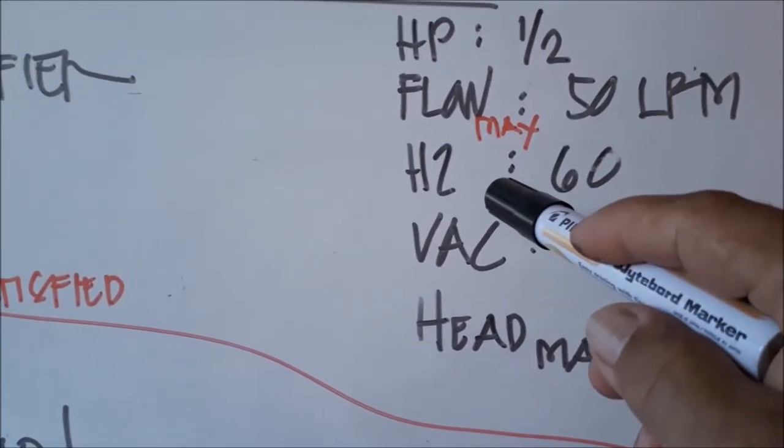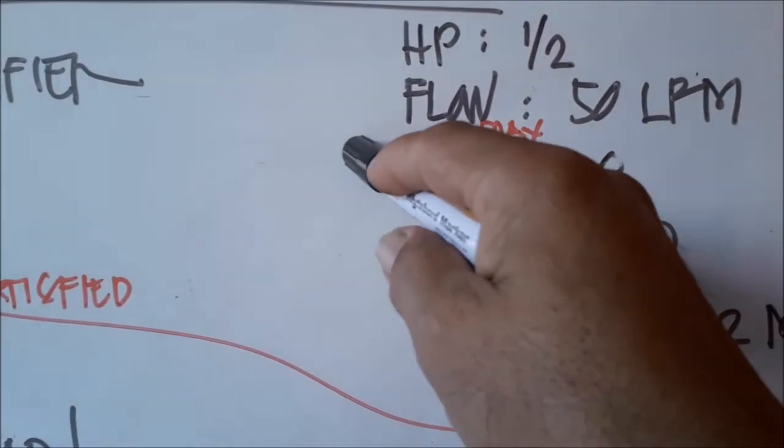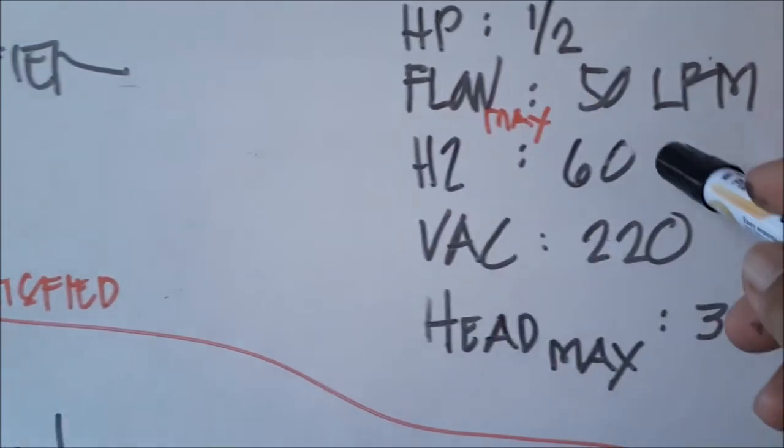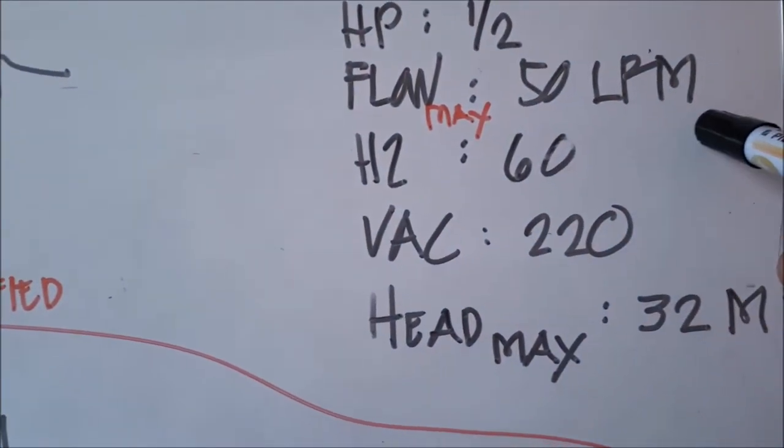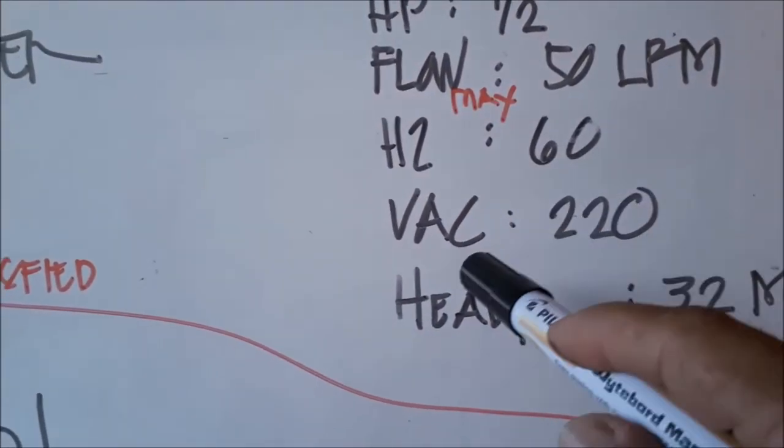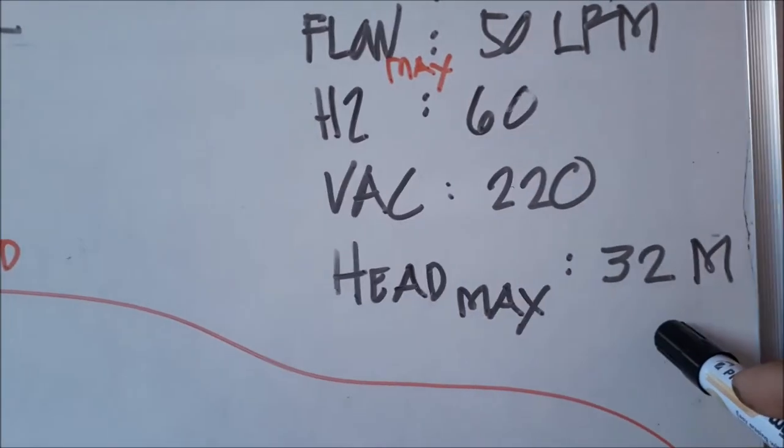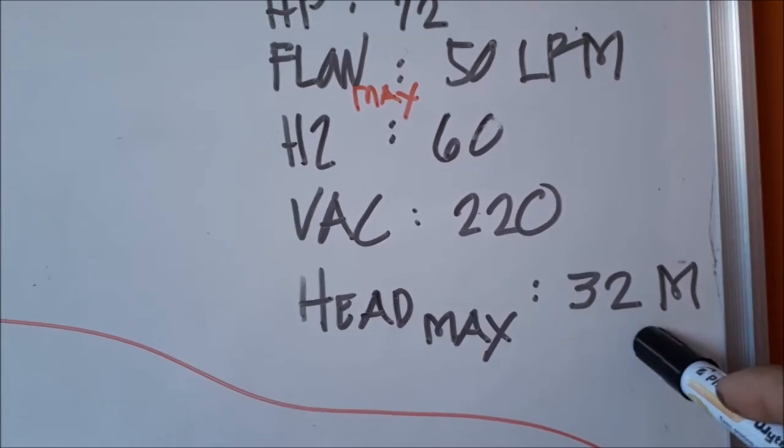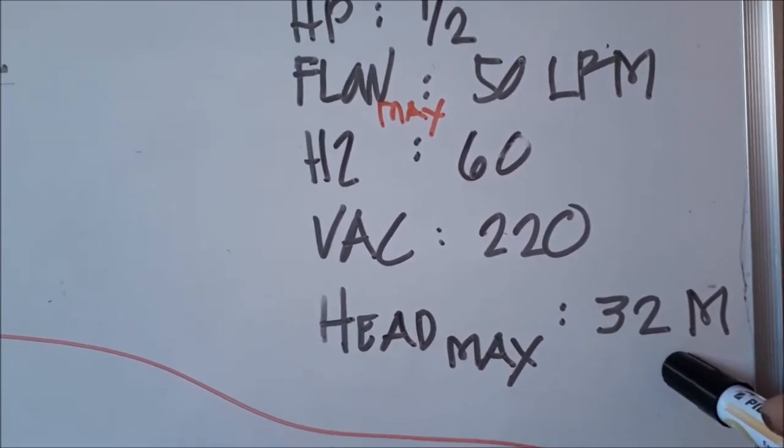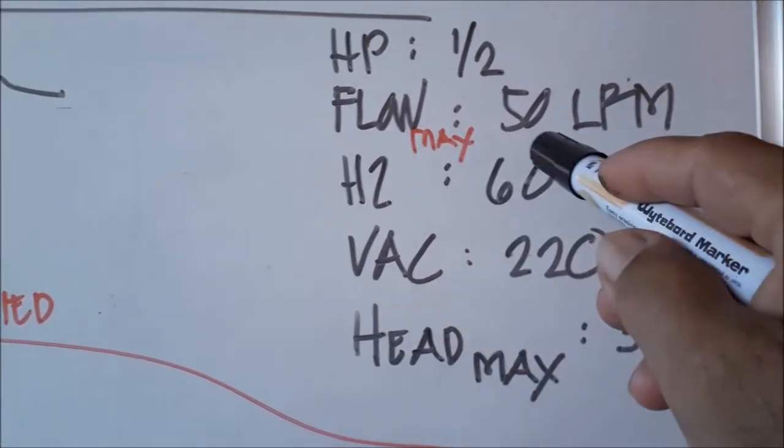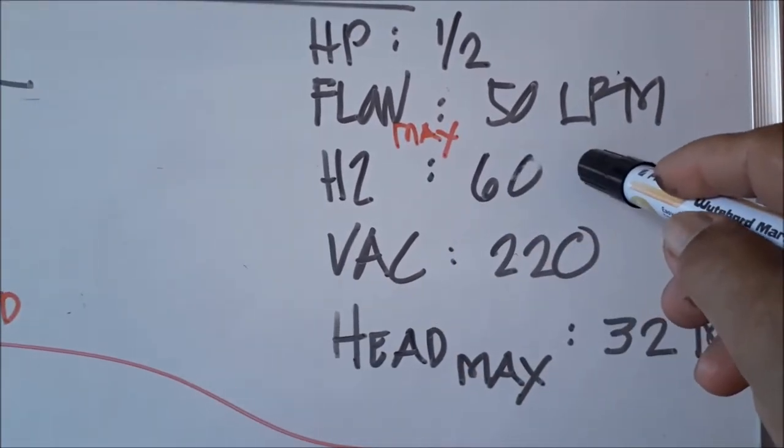The design flow, or maximum flow that it can attain, is 50 liters per minute. Its hertz is 60, voltage is 220, and its maximum head is 32 meters. This means at 32 meter maximum head, its flow at that height is 50 liters per minute maximum.